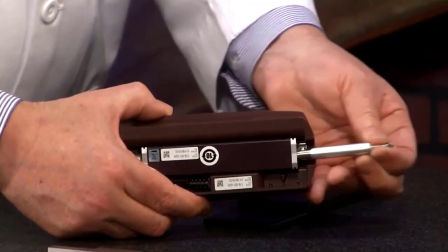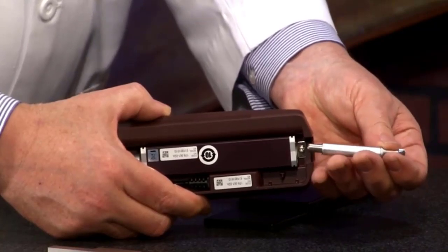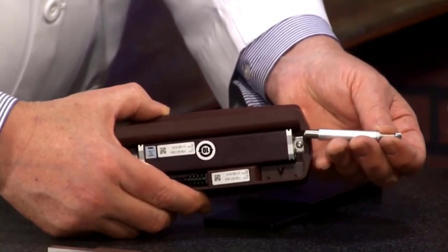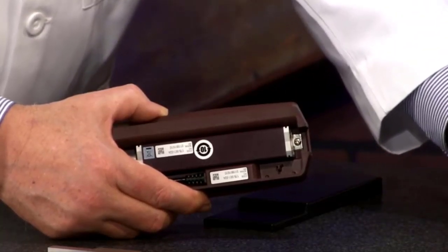They make different types of probes for this. These come out, these pull out. Let me show you how this goes. They pull right out and they're replaceable because they do wear out also. Sure, they're rubbing across stuff all the time. And when we calibrate them for customers, we sometimes give them the bad news. They get to buy a new probe because they do wear out.